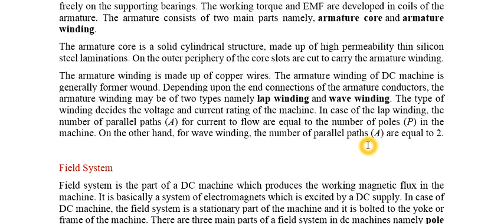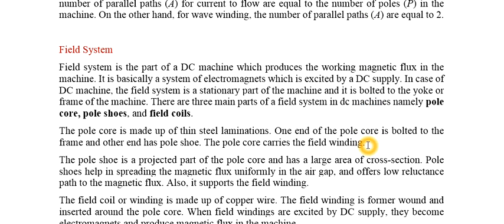The number of parallel paths depends on the winding type. In lap winding, the number of parallel paths equals the number of poles, whereas in wave winding it is always equal to two. Next, the field system — the poles and field windings together — provides the working magnetic flux in the machine.